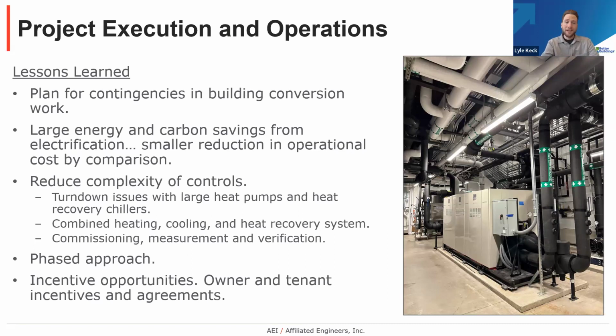Lastly, reducing complexity of controls. When you start to look at large heat pumps, they have turn down issues. They want to operate continuously at higher loads. And now you're taking separate cooling and heating systems and often combining them into a combined heating, cooling, and heat recovery system, which is just inherently more complex to operate. And so trying to minimize complexity during design, even if it makes some trade-offs to the optimal efficiency or the optimal strategy, simplifying complexity in selection and design helps a lot, as well as thorough commissioning, measurement, and verification throughout all seasons and throughout the maturity of the building as it gets fully utilized and fully populated.